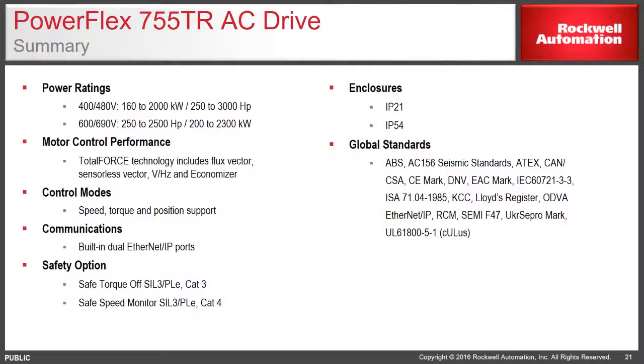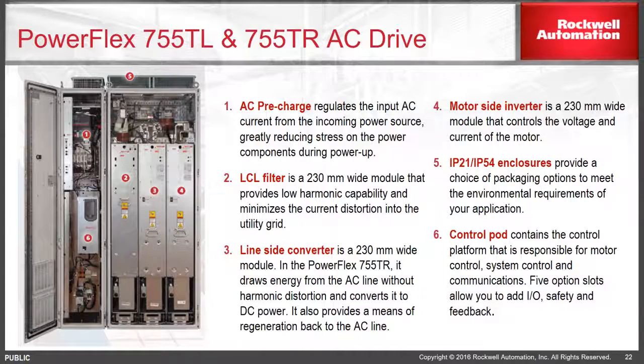The 755TL and TR have the following features. There's an AC precharge that regulates the input AC current from an incoming power source, greatly reducing stress on the power components during power up. There's an LCL filter, which is a 230 millimeter wide module that provides low harmonic capability and minimizes the current distortion into the utility grid.